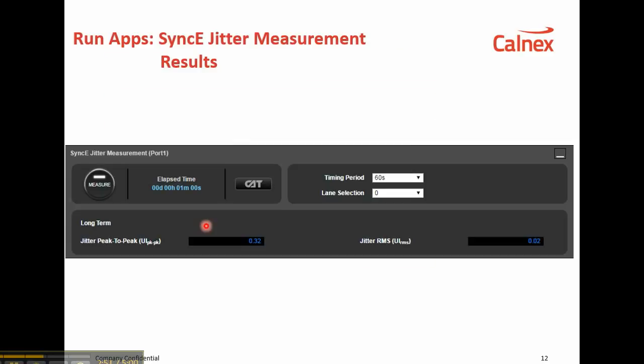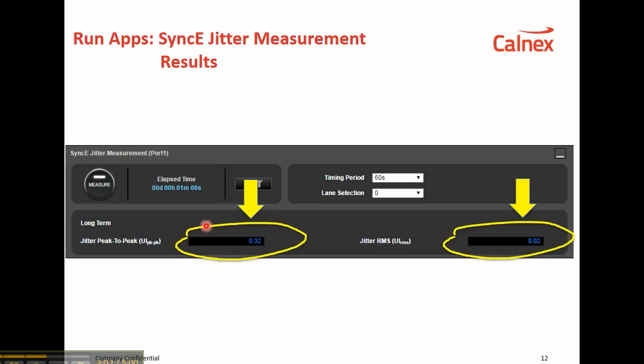Finally, this shows the result now that the jitter measurement is complete. The peak-to-peak jitter result is 0.32 UI peak-to-peak as shown here, and the RMS jitter result is 0.02 UI RMS. Of course, it's the peak-to-peak measurement that we're interested in here.